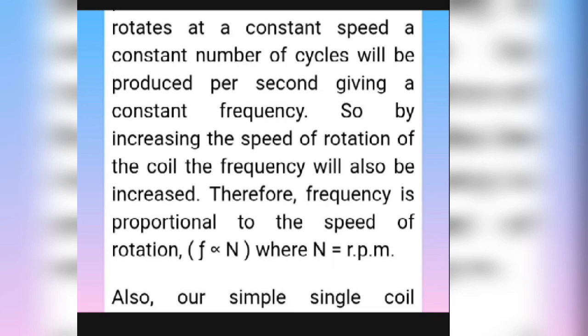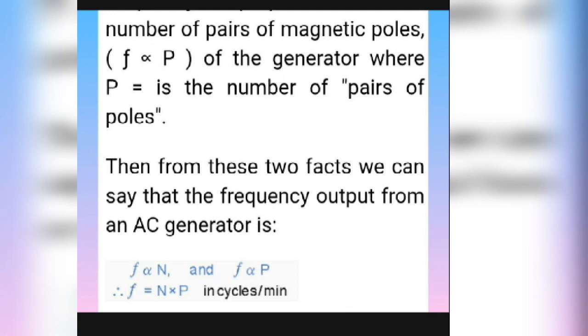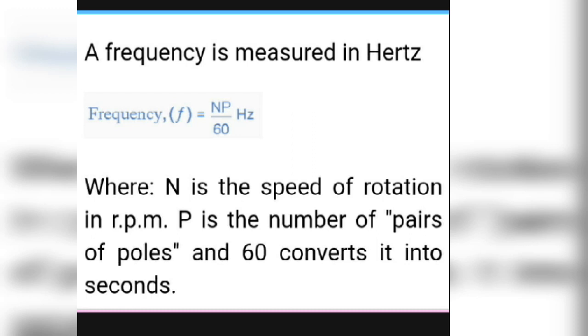For a simple single coil generator, the number of pairs of magnetic poles also affects frequency: F is proportional to P, where P is the number of pairs of poles. Combining these two facts, the frequency output from an AC generator is: F = N × P in cycles per minute. Since frequency is measured in Hertz, the full formula is F = (N × P) / 60, where N is the speed of rotation in RPM, P is the number of pairs of poles, and 60 converts minutes into seconds.